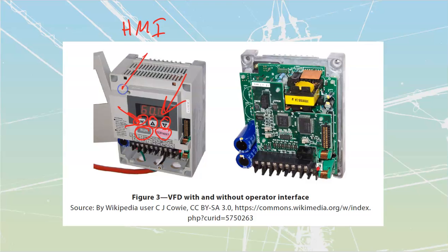When you pull this cover off, in a lot of cases it removes the whole HMI directly off of there. Oftentimes the HMI is plugged directly in - over here you see we've got a set of buses where that HMI will plug directly into. Other times it's ribbon cable connected. And then we've got a whole set of terminals down here at the bottom. Those terminals are going to have all of our motor connections, as well as additional control connections that are often made on them as well.